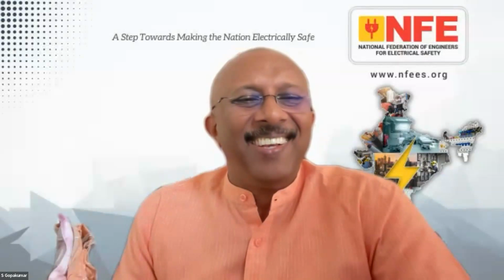I would like to clarify one more thing here. There is a lot of misconception prevailing within the community regarding double earthing. A lot of people use one earth for the main motor terminal, and the second earth they try to put anywhere, on the high beam or elsewhere, so that is not effective. Let's understand clearly.